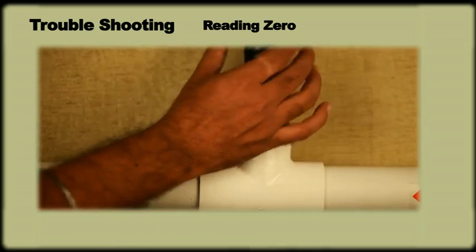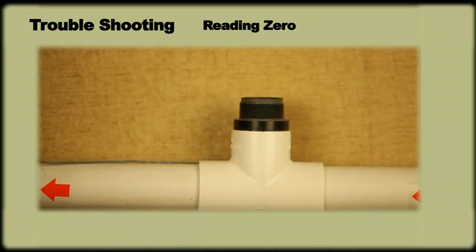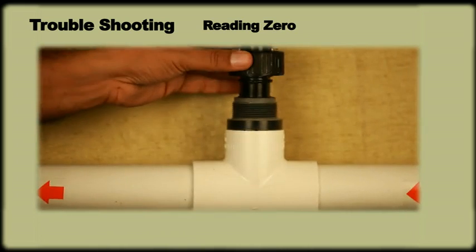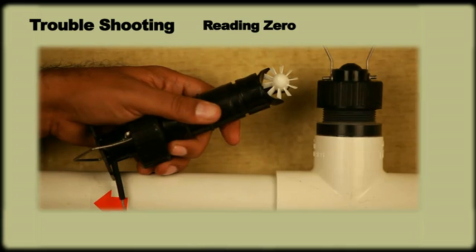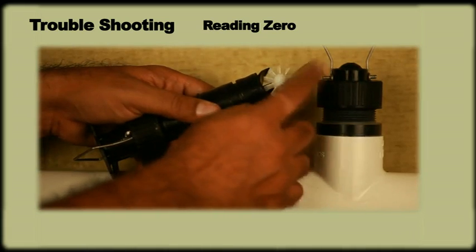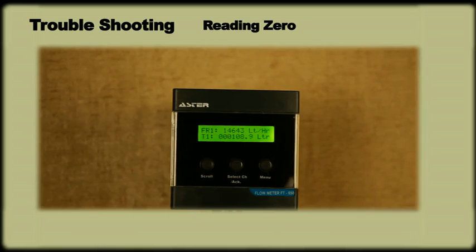Then remove the sensor from the fitting and put a blind plug on the line provided with sensor. Check the change in reading by physically rotating the turbine. While physically rotating the turbine, if the display shows some reading, then it implies that there is no fault with the meter or the sensor.